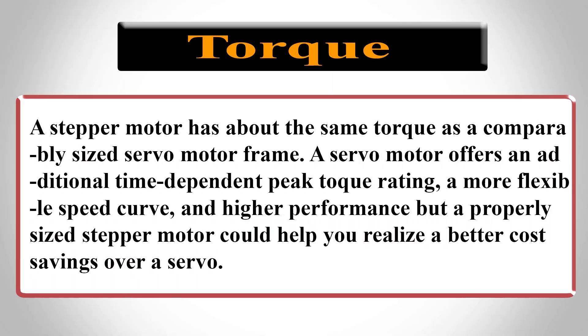Torque: A stepper motor has about the same torque as a comparable size servo motor frame. A servo motor offers an additional time-dependent peak torque rating, a more flexible speed curve, and higher performance, but a properly sized stepper motor could help you realize a better cost savings over a servo.